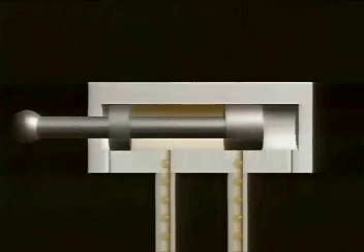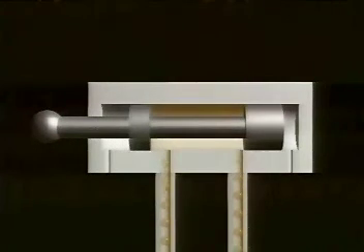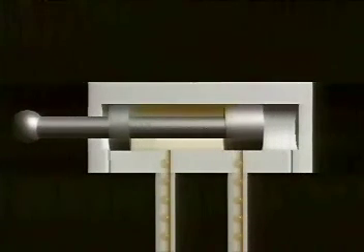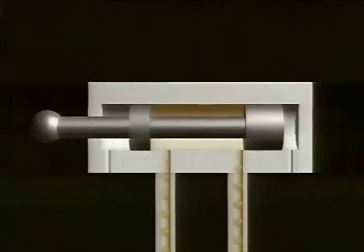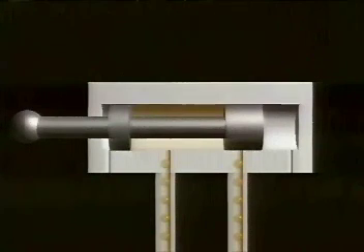The piston needs a certain amount of tolerance, which is why this type of valve doesn't seal as tightly as poppet valves. So, they are only used for pressures of up to 315 bar. Spool valves can open or close more than three ports at once.